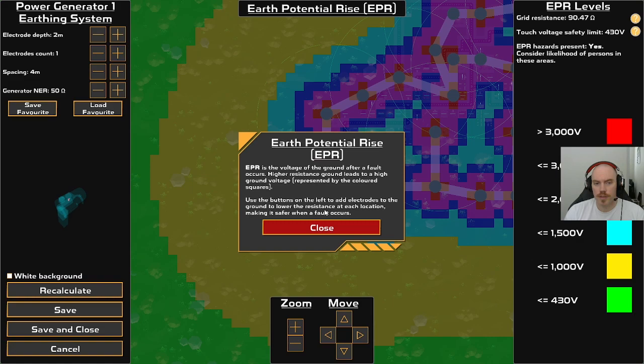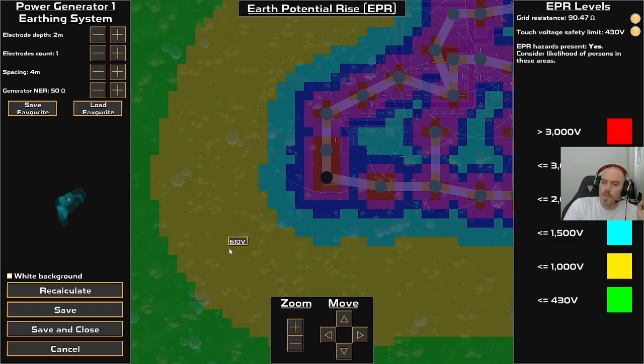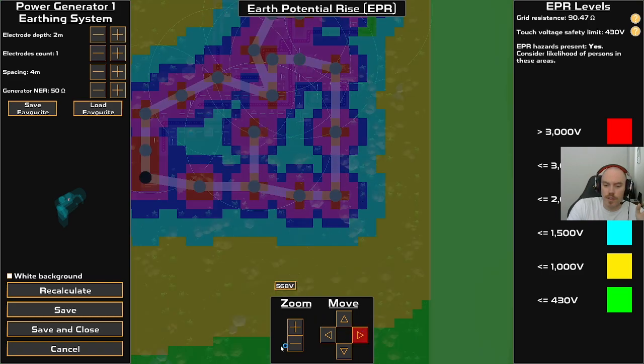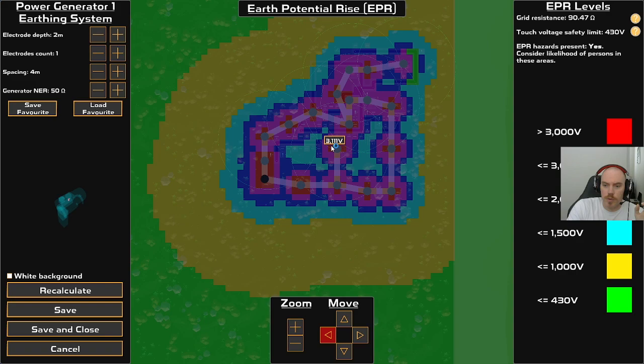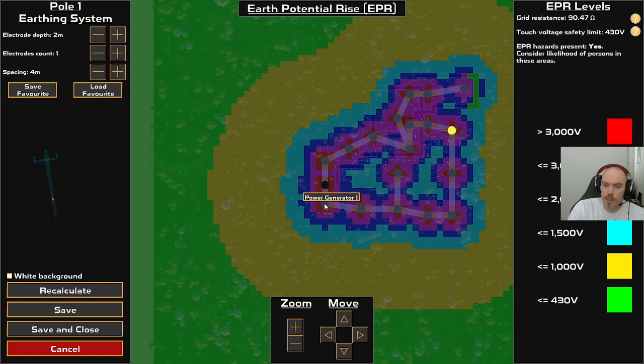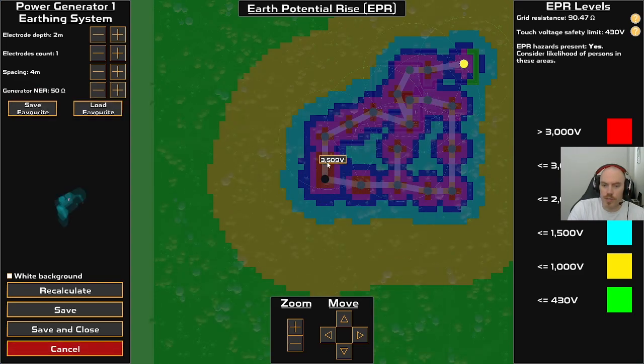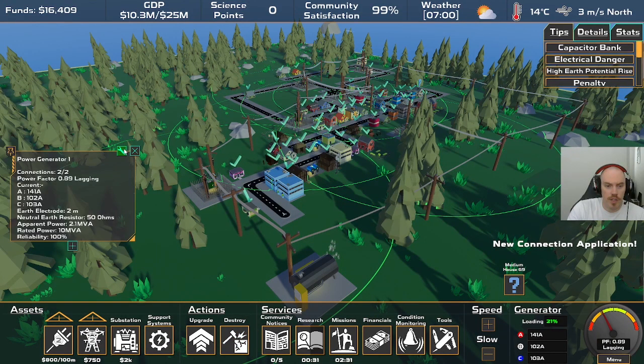I've developed a tool here, similar to one an earthing expert, like a power engineer who specializes in earthing or grounding, would use. This is an overlay of the town or electrical network I've built. You can see the ocean out here, and it shows the voltage that occurs if a fault happens on the load I've selected, whether that's the pole, the generator, or the substation. You can see the representation of this string here.